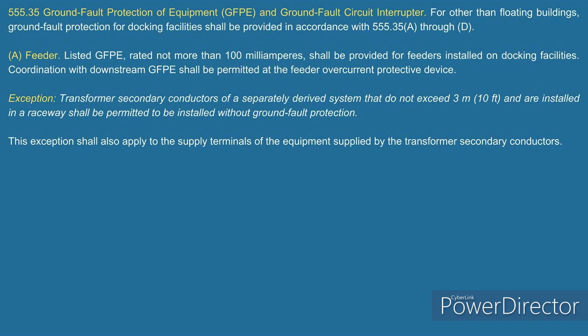Matter of fact, if you go look at Article 314, the very first word in there that deals with all your different boxes and everything, it says outlet. Okay, you're talking about 314. I mean 314, Article 314. I'm sorry. Now, let's look at the section, see what it says here. It says, for other than floating buildings, ground fault protection for docking facilities shall be provided in accordance with 555.35(A) through (D).